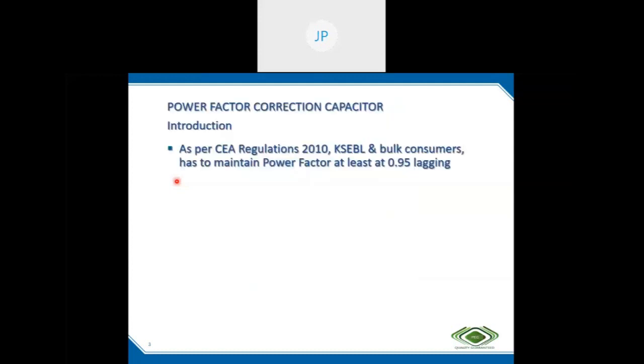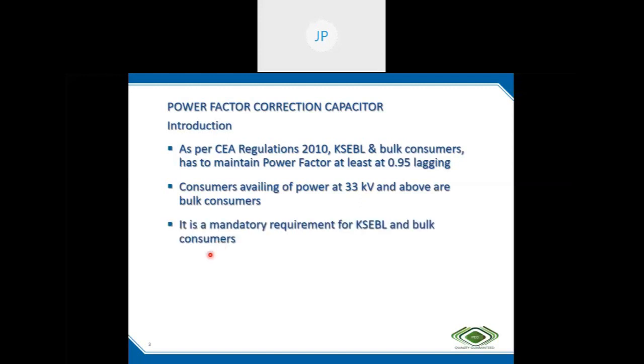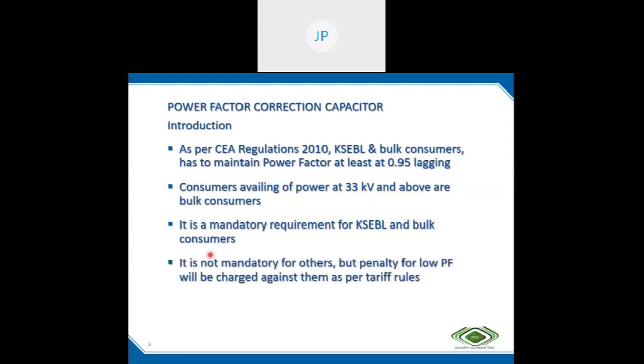KSEBL and bulk consumers are required to maintain power factor at 0.95 lagging as per CEA Regulations 2010. Consumers availing power at 33 kV and above are bulk consumers. And for these consumers and utility, it is a mandatory requirement. For others, like LT, HT, it is not mandatory, it is optional.